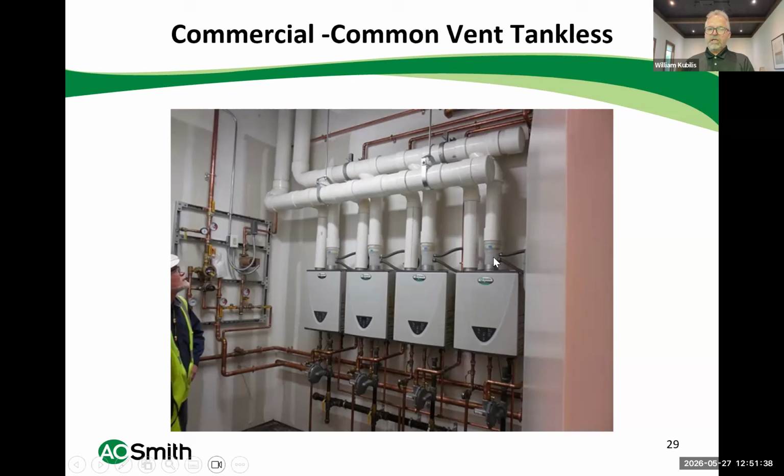That accessory is there in the event that one heater is down for service and somebody took the panel cover off, that the exhaust of the operating units could not come back into the room and put carbon monoxide or vent products into the boiler room.